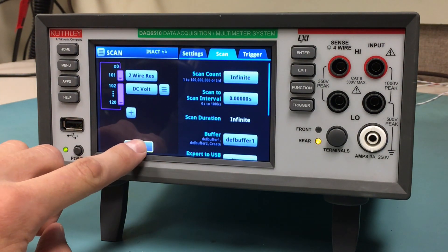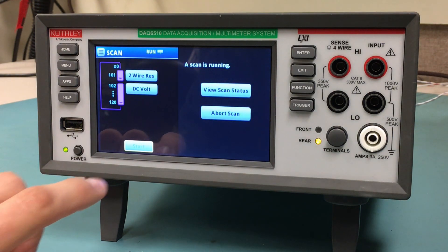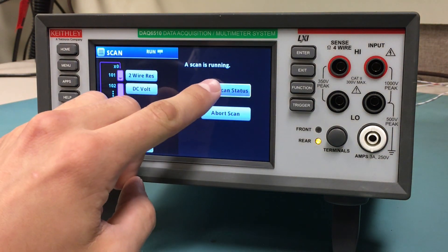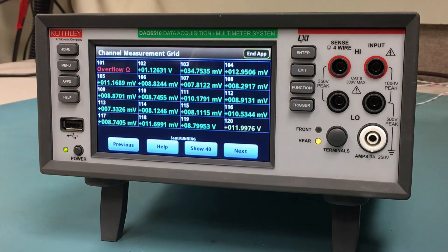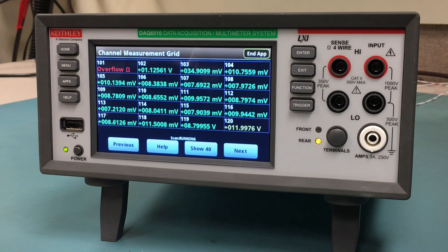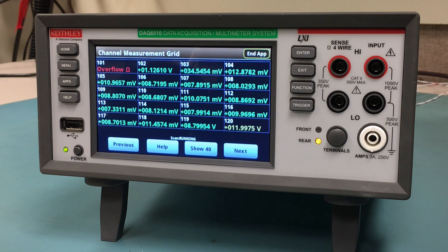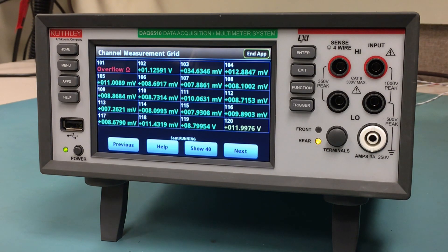Next, hit the Start button and view Scan Status. The Channel Measurement Grid will then populate with readings across the 20 channels. As you can see, Channel 20 is displayed in yellow, showing that it's above the limit, and Channel 1 is reading an overflow, displayed in red.